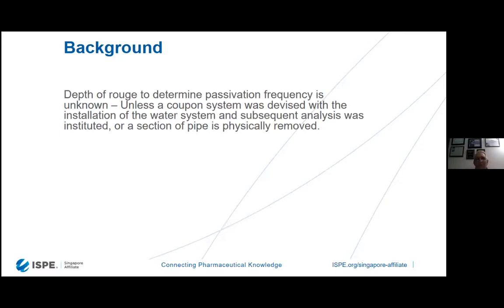At one time, we were looking at coupon systems that were put into the water system in order to see if we could measure rouge on a coupon, take out the coupon, then send it off to a laboratory. Of course, the coupons were extraneous to the water system, which means that we had to put them inside, making them invasive, and then we had to pull the coupons out, shut down the water system, and send them off to a lab. And then we would get a reading back and people would say, what do I do with this information? And no one knew. So they got rid of the coupons.